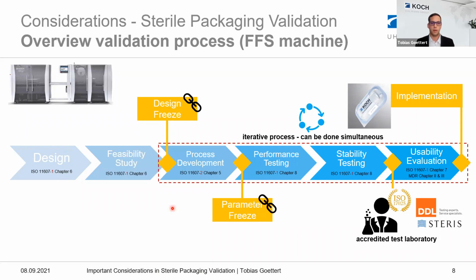And if you think, okay, my design meets the requirements, then you do a design freeze. If you then change something bigger, you have to justify whether you have to revalidate or not. Then we are in an iterative process. After the design freeze, you create your first prototypes and samples, and then you go through different steps. Let's start with the process development. Here you have to define your parameters, like the sealing parameters: temperature, sealing pressure, and sealing time. And you also have to do performance testing and stability testing. I have separate slides next for these three points, and you can do them mainly simultaneously.